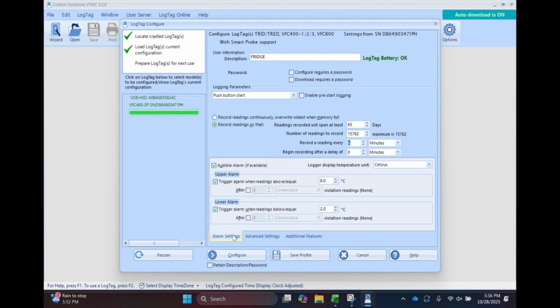Moving down below to our alarm settings tab, you can see in the top left we have the audible alarm that is enabled, because we want to hear the logger beep if there's a temperature excursion. We have it set to Celsius. This is where you would change the logger itself. Earlier we changed the software to Fahrenheit, but here is where you would change the logger itself.